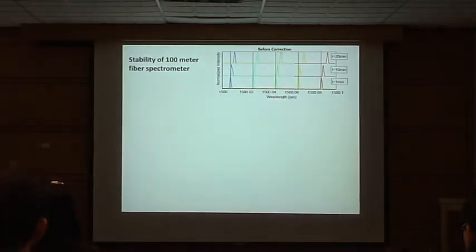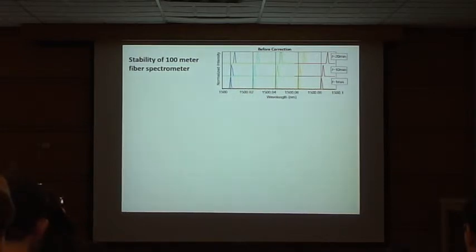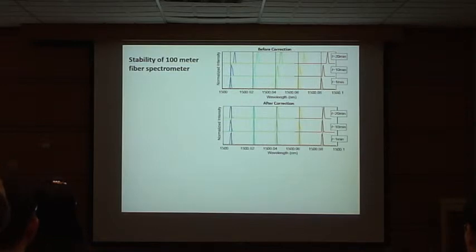So how can we recover it? We realize that for different wavelengths, all the lines are shifting the same way. So that means if we have some standard frequency of the light, in neon, very stable, we periodically measure what that is, and then we try to correct it. If we can correct one of them, all of them will come back. Okay? This is just a software correction.